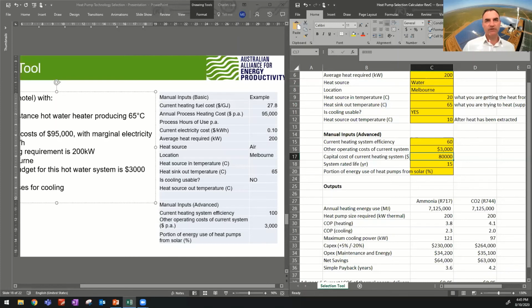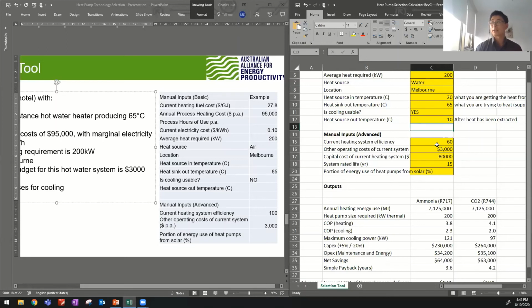Maximum heat out temperature: yes, there is a cap. Right now it's capped at 85 degrees, so if you put in 90, it won't work. We're looking to expand that cap because we now have a bit more data on 90 and 95 degrees. By the time this tool goes live, I expect it to be at least 90 degrees. In the future, once steam replacement versions of these heat pumps become available, that gets stretched out a little more. But at the moment, it's at 85.